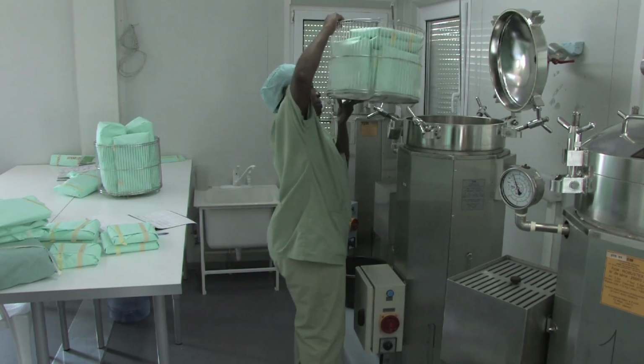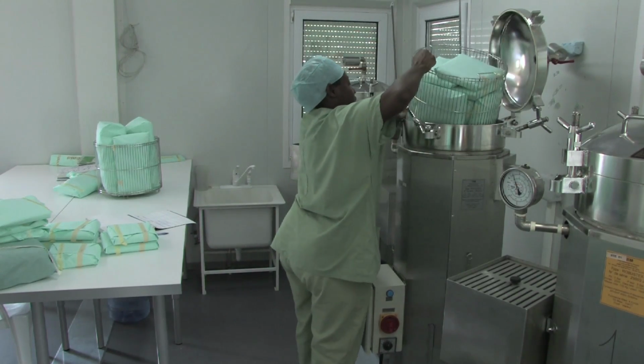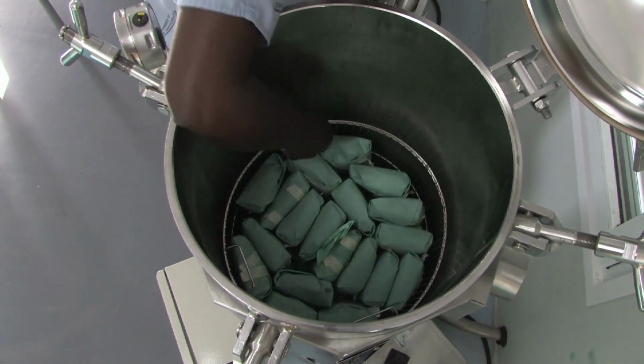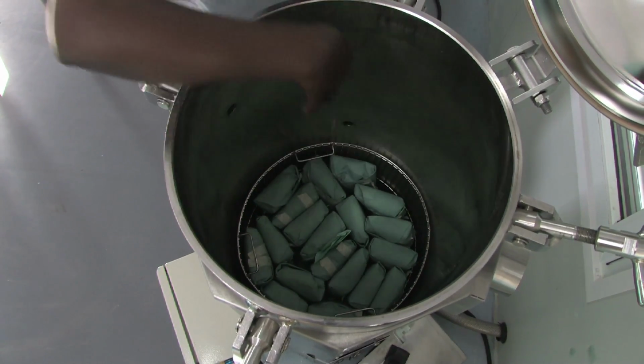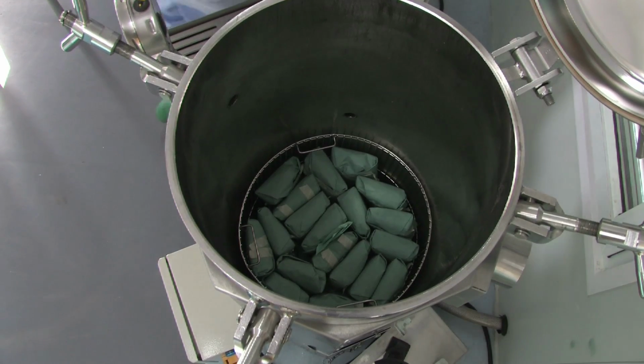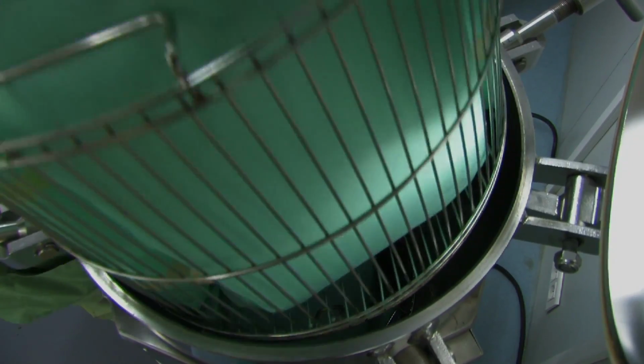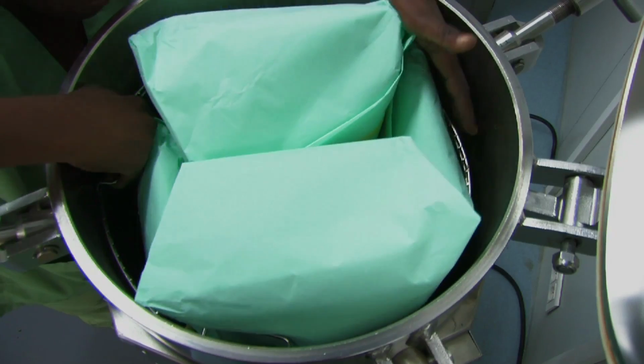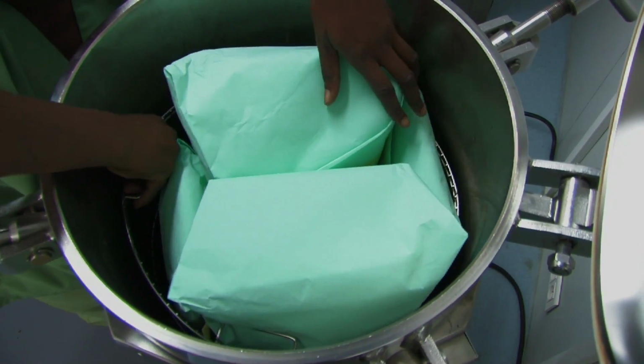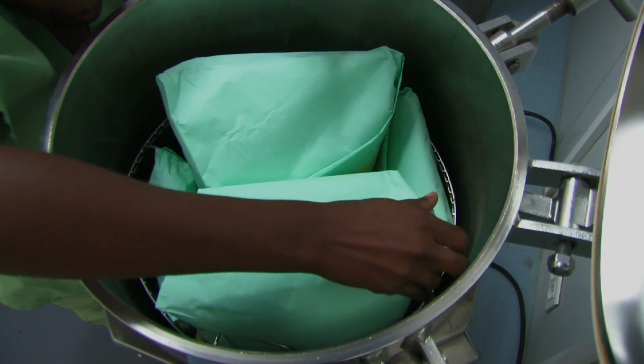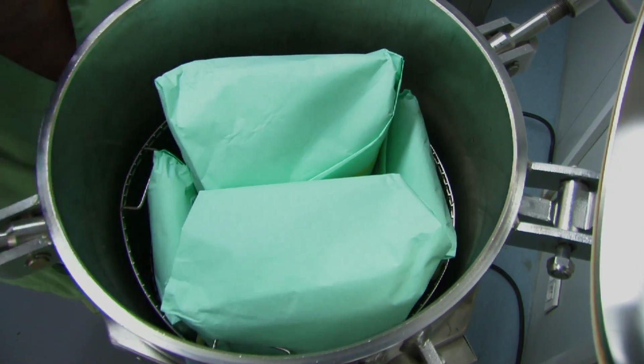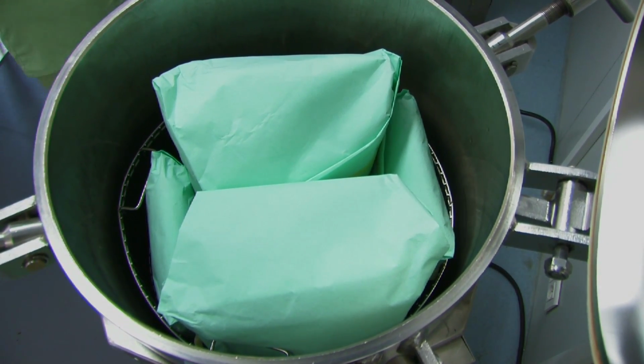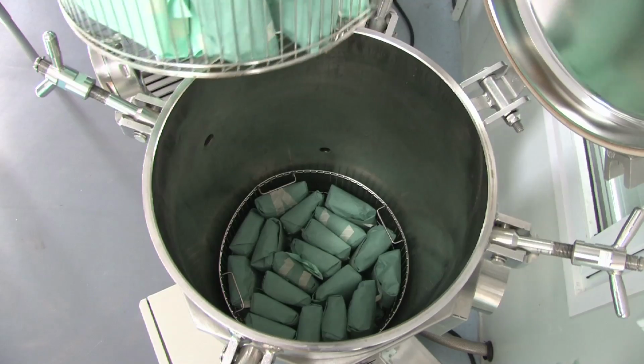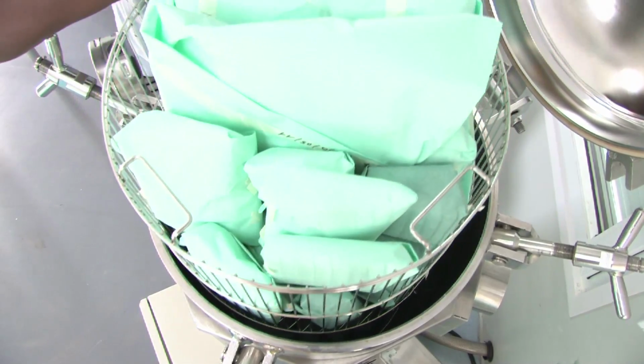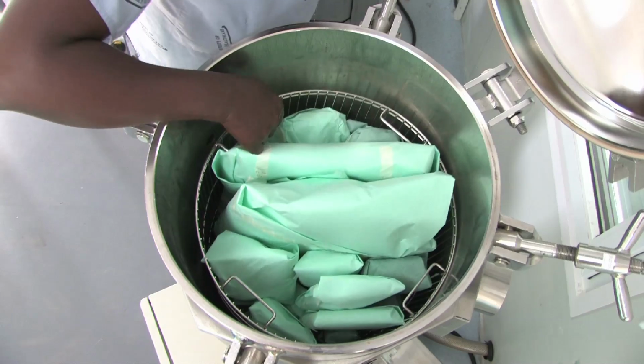4. Place the baskets in the autoclave. Do not overload. The autoclave chamber should not be more than 2/3 full. If there's too little free space, there'll not be enough steam for good quality drying. Make sure that the packs do not touch the walls of the autoclave, otherwise they may get wet when the steam condenses along the walls. Both baskets must be used.